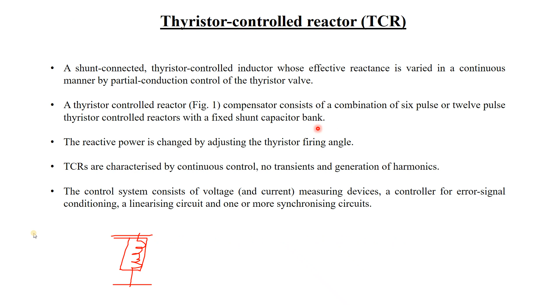Now this is the equation for the TCR reactance. So the TCR reactance is XL. This is the equation, where alpha is the firing angle. Which means that in a TCR, if I go back to the TCR once again, this TCR is a thyristor controlled reactor. So the reactor is there. This is the current limiting reactor. This is the actual reactor of the line. So the reactance of the line depends upon the firing angle of the thyristor. That is why in the equation, XL is a function, with alpha in the bracket.